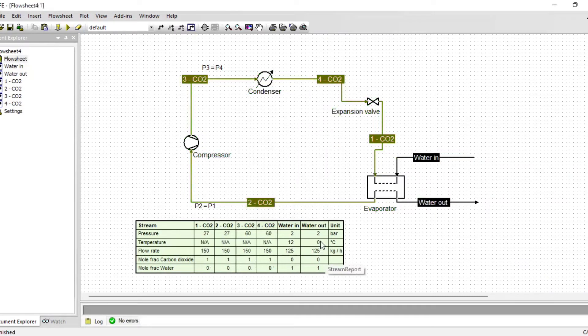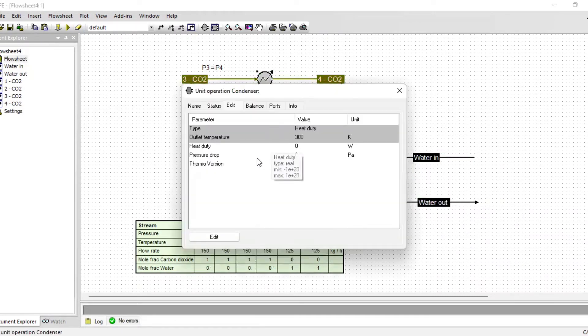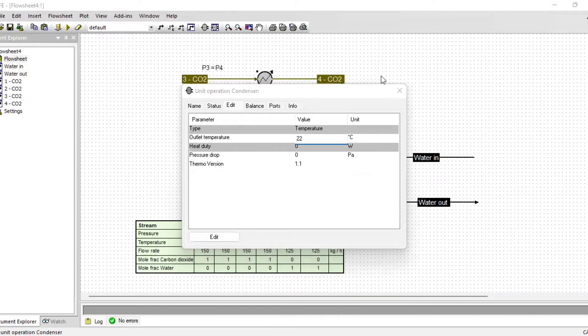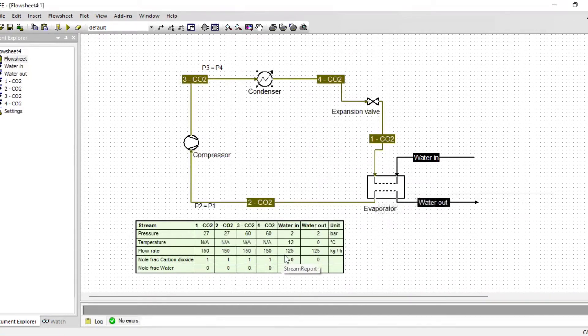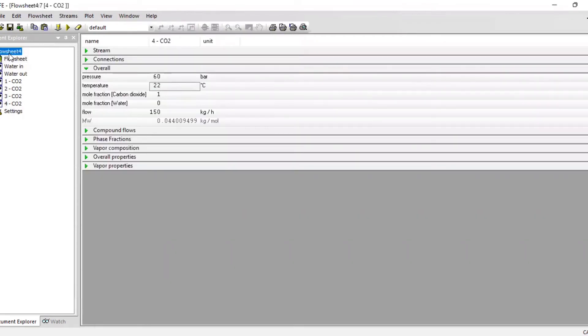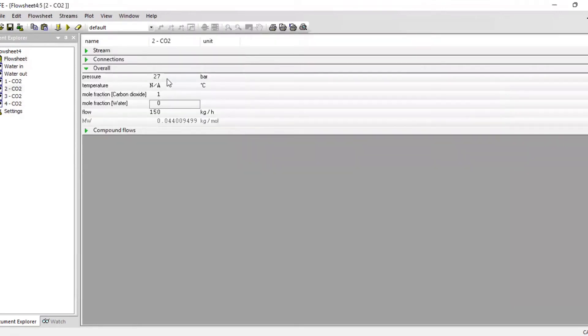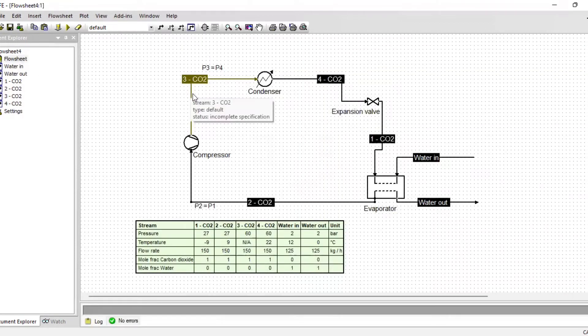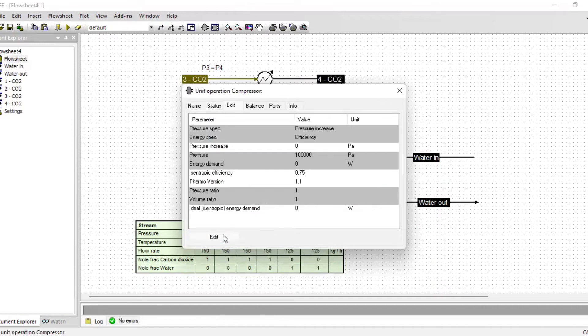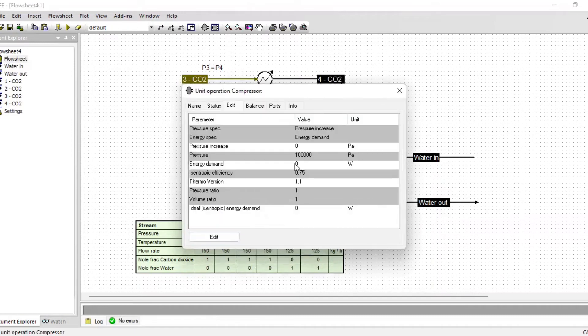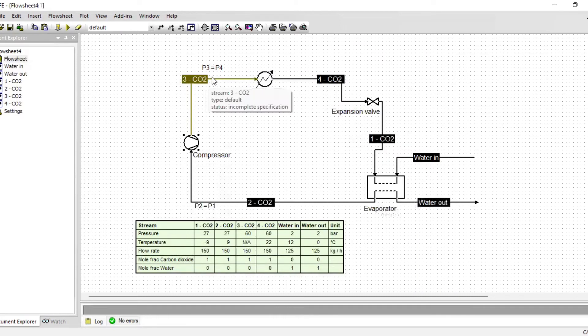It's not making sense, so I'm going to reset everything. For the condenser, we want an outlet temperature of 22 degrees. For the expansion valve, the temperature will be around minus 10, ranging to minus 9, 8, 7, or 5 — the temperature is expected to decrease as it comes down. The temperature after the compressor is going to be extremely high, influenced by the power required here. Let us set that energy demand to 3.91 kilowatts and run the file.